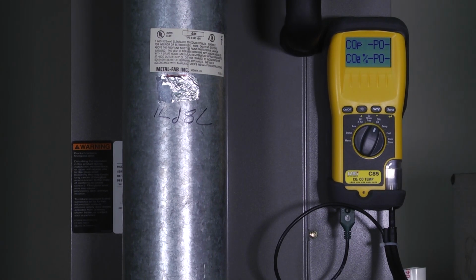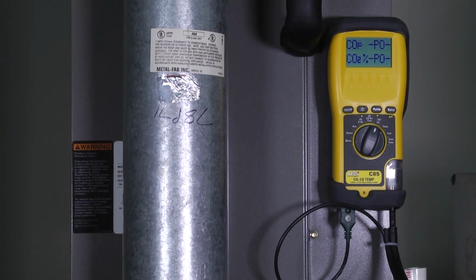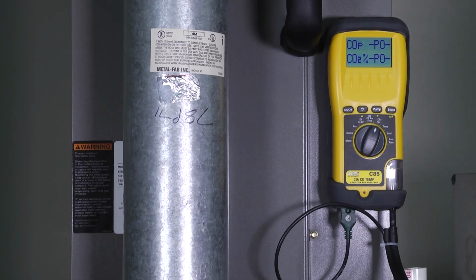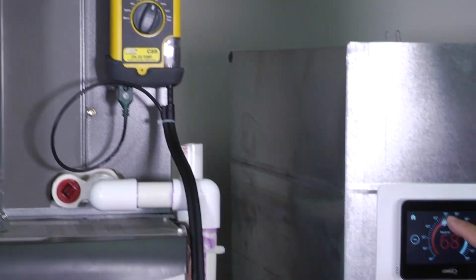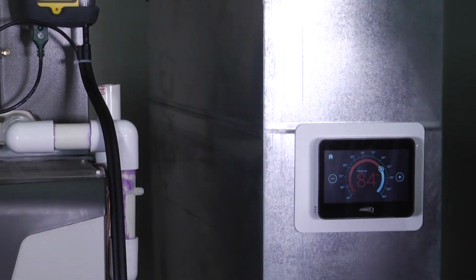Have you ever had that question where you think to yourself, I wonder if that heat exchanger is cracked? And I start looking at it, I try and get inside of it. Do I cut the side out? Do I start cutting holes in ductwork? Do I start looking inside of it? How about the first thing we do is we take a look at the flue gas analyzer and see what it's telling us. In a system like this, we've got the flue gas analyzers, we've got the system heated up. So what I'm going to do right now is just turn the furnace on and we're going to take a look at it.